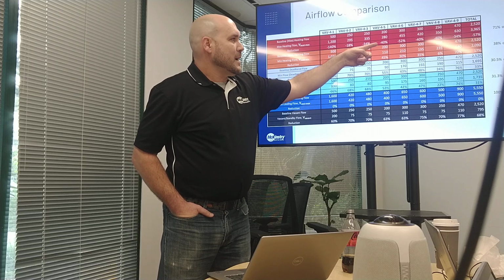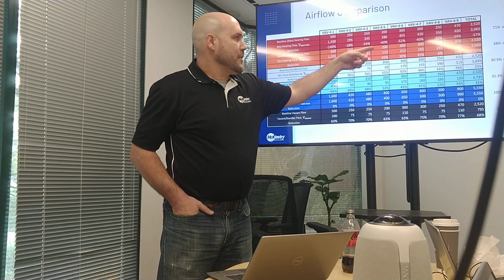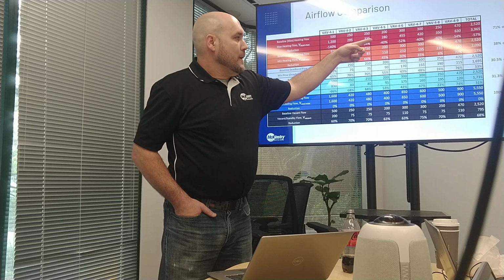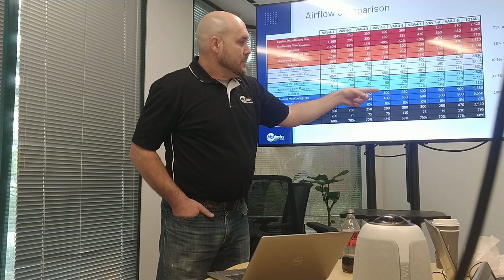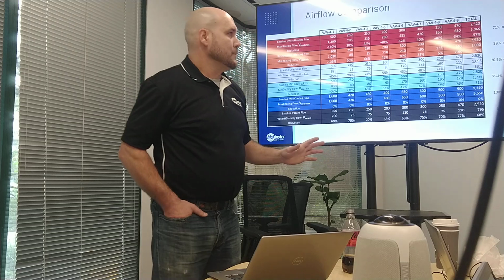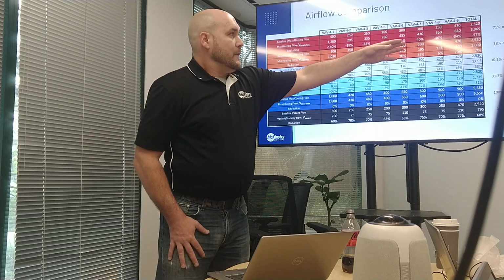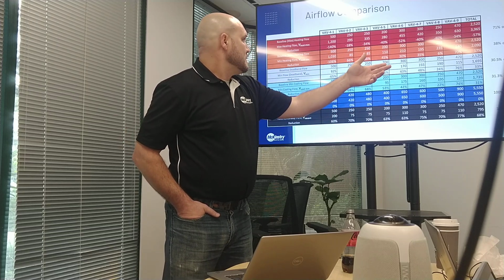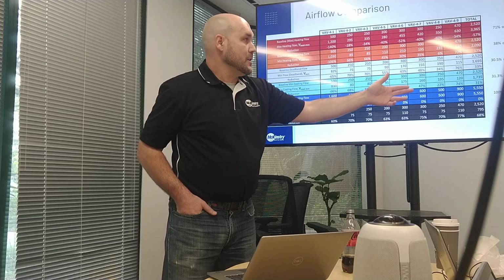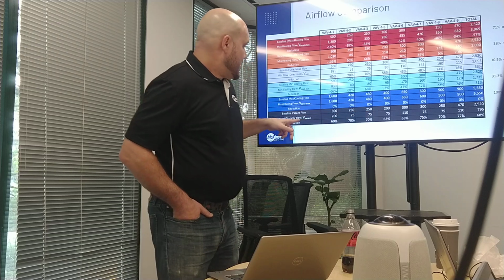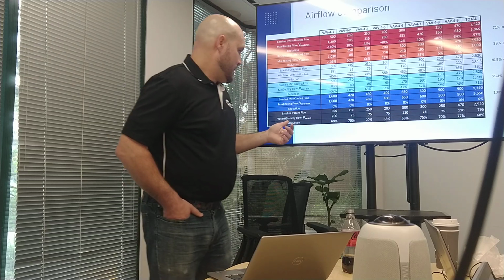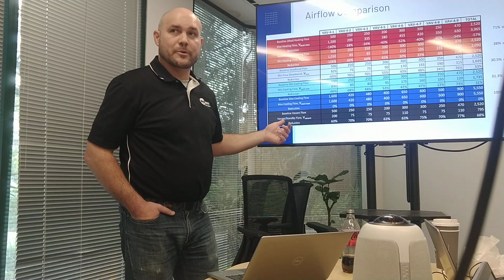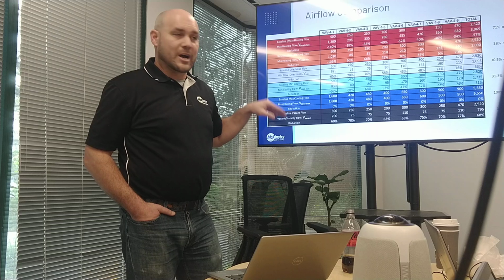So it is actually a slight energy penalty, but the amount of time that the box spends there is minimal. It's very, very infrequently at full heating. So the amount of savings that you see in all these other modes more than offsets that by like tenfold. So yeah, kind of on average, you can see that heating mode is 71% of design flow on average. The baseline minimum heating is only 38% of design flow. The big thing to take away from here is that 14% of design flow is the vacant or standby mode. So that's really where the opportunity is to drive boxes down.